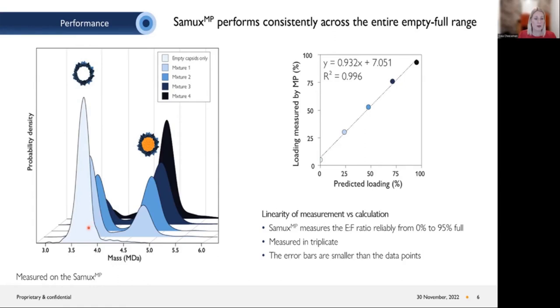Starting with measurement of different empty/full ratios — from 100% empty to almost 100% full — you can see the empty peak on the left and the full peak on the right. We created these by mixing empty and full AAVs in defined ratios and then measured the empty/full ratio with the system. Plotting the predicted loading based on mixing versus the loading measured by the mass photometer, you can see it is very accurate and shows a really nice linear relationship all the way from 0 to 100%, confirming we can accurately determine the empty/full ratio across the entire range.